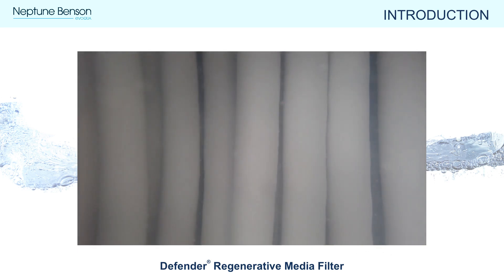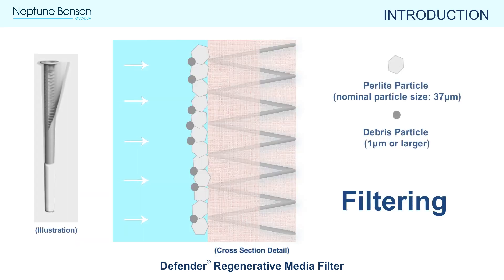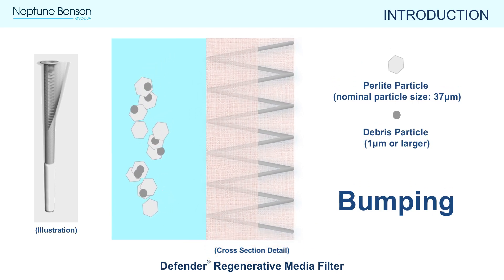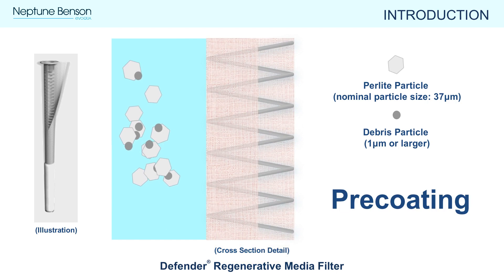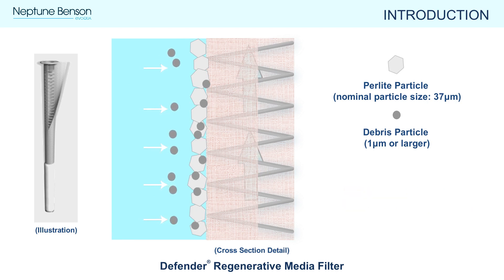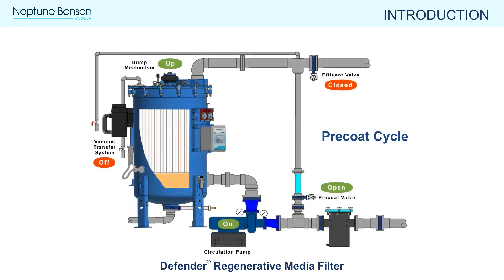While precoating, some perlite may be seen at the precoat sight glass. As perlite adheres to the flexible tube elements, the water in the precoat loop will clear. The purpose of bumping the filter is to disrupt the perlite coating on the tube elements. Once all the perlite is mixed up and in solution, it then gets reconfigured into a fresh layer during the next precoat process. Once precoated, it is ready to collect more dirt and debris. Important to remember: the perlite media is the filter, and the tube elements are simply a framework for that filter media to adhere to.